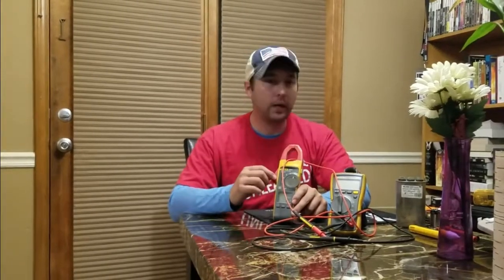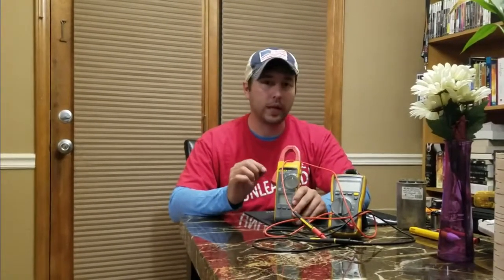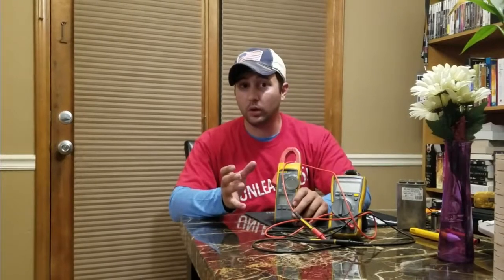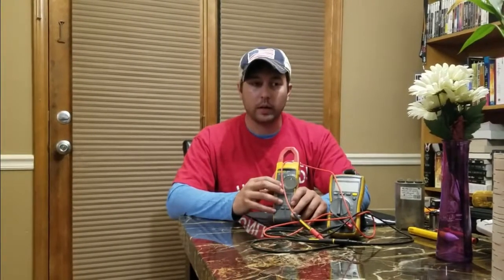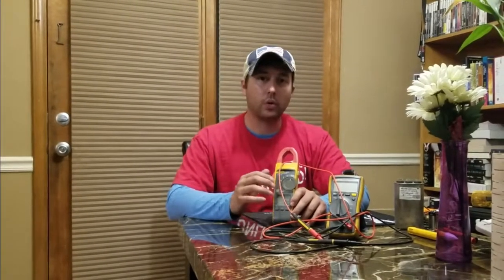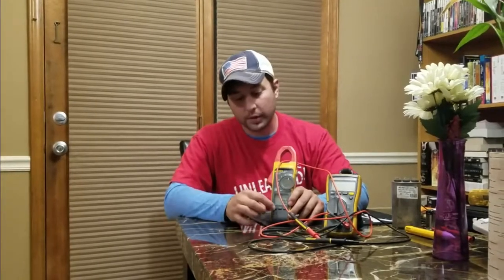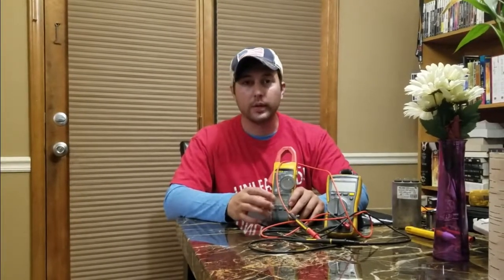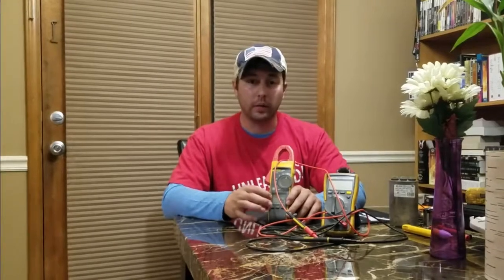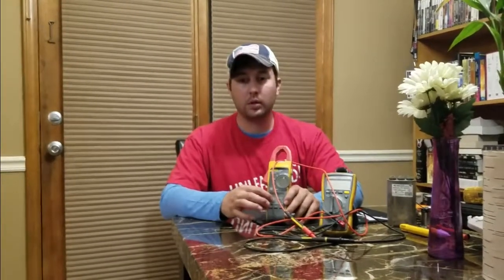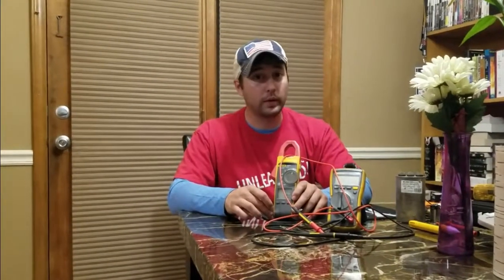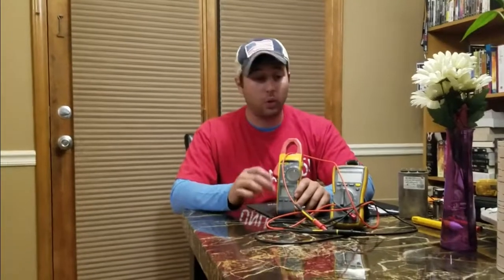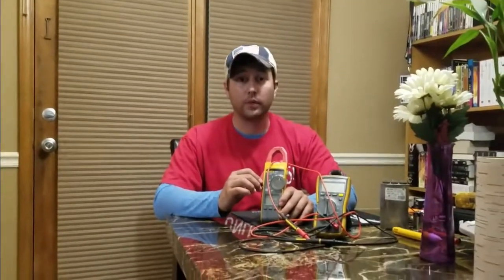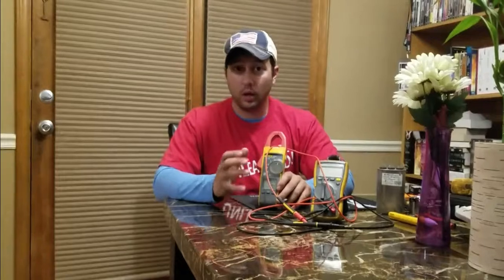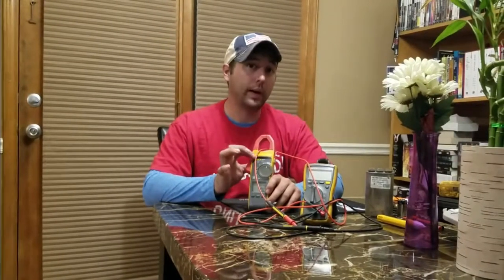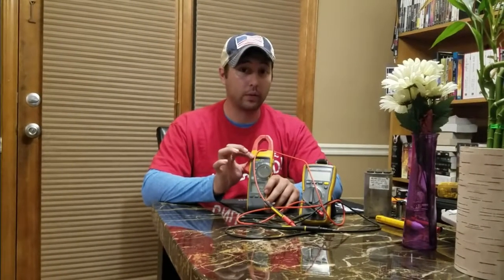If we look on the side of our motor, it'll tell us how many amps it's rated for. And if it says this motor's rated for 1 amp, and we're registering 3 on our meter, we know there is a problem with our motor. Either a bad connection, not the correct power going to the motor, or it's quite possible the motor itself has just started to fail. That's why that is a very, very handy feature for diagnosing something.